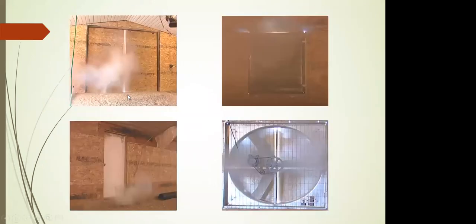Similarly, you can see these four pictures. These two show that the leakage has been through the doors, the opening of the doors and the lower compartments of the door. And in these two pictures, you can see that the fan shutters are facing some issues with leakage around the corners and also with their central shutters.